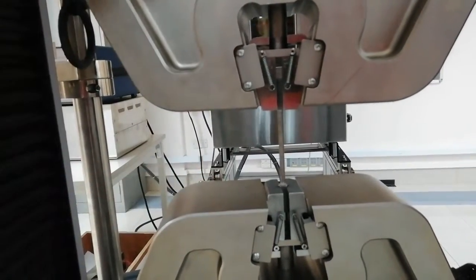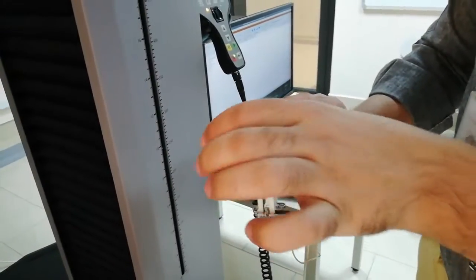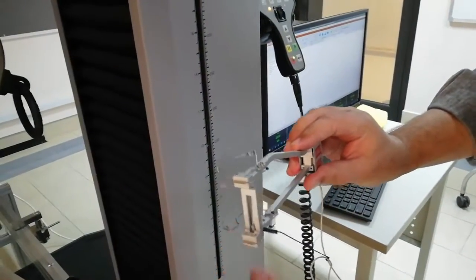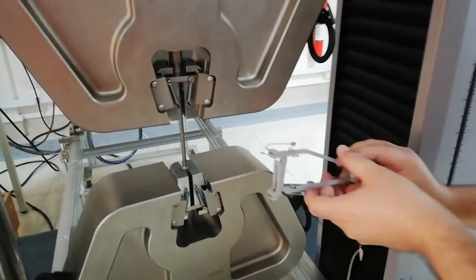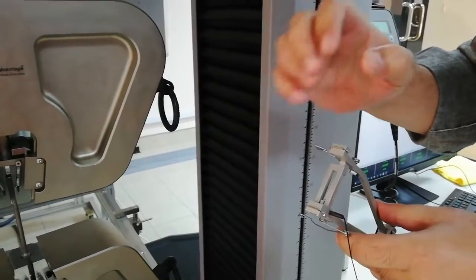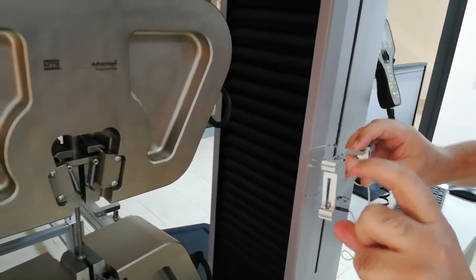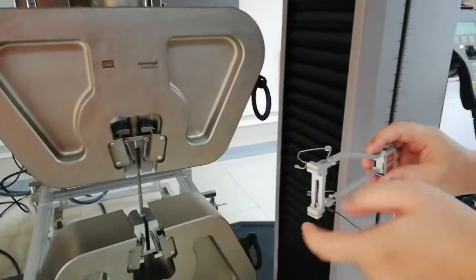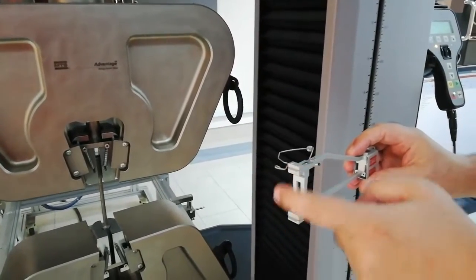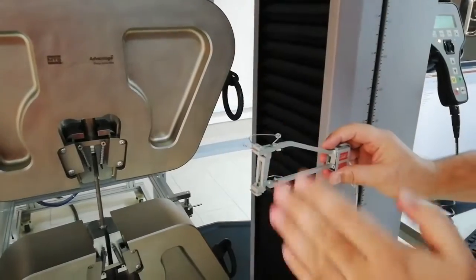Once we start the experiment, we receive the load from the load cell, but the extension from the crosshead is not very accurate. So we use a special device — the extensometer — which is highly sensitive. It has two flat surfaces; the distance between them is the extensometer gauge length, which is 50 millimeters. We fix it on the specimen and the software takes the deformation — the elongation — via these two blades, which is much more accurate than the crosshead. We have this pin — we should not remove the pin before we install the extensometer onto the specimen.